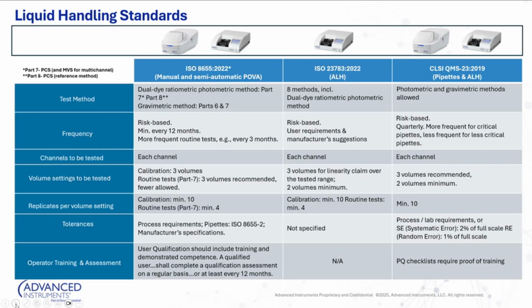So let's round it full circle with CLSI QMS 23. Again, that's the standard that a lot of our clinical customers will follow and adhere to. They mention a couple of different test methods in their standards. A photometric method, as well as a gravimetric method, is allowed. They also mention frequency. Those 2 words, risk-based, are also mentioned in QMS 23, but they recommend a quarterly calibration, which is interesting, right? That's a bit more frequent than what ISO recommends. But they also indicate that maybe it's more frequent than quarterly for critical pipettes and less frequent for less critical pipettes.